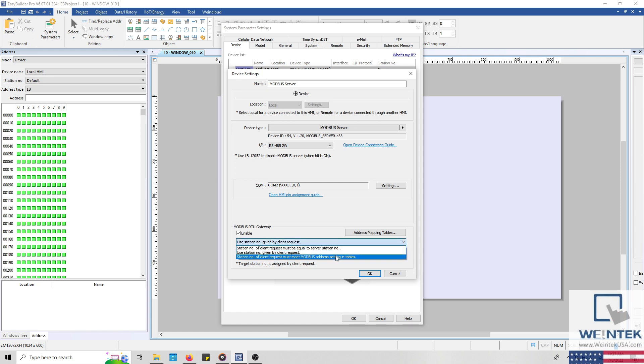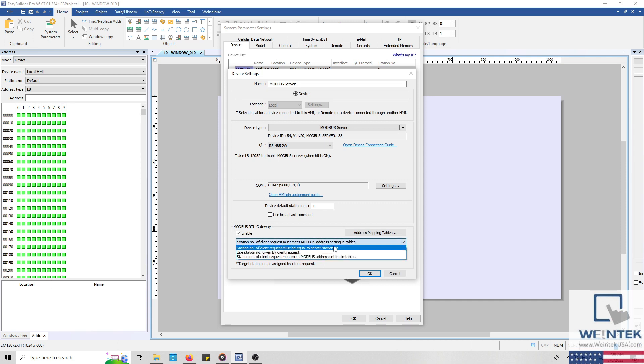And when station number of client request must meet Modbus address setting and tables is selected, the station number must be configured within the address mapping table using the following syntax: Station number, hash, and then the Modbus address. During this demonstration, I'll leave the default option selected within the drop-down list, and we'll click the address mapping tables button to review the configuration of our tables.